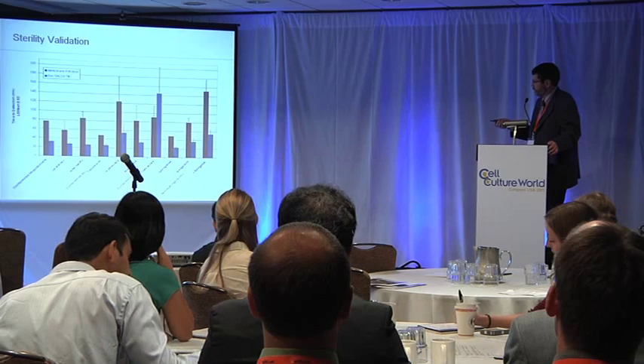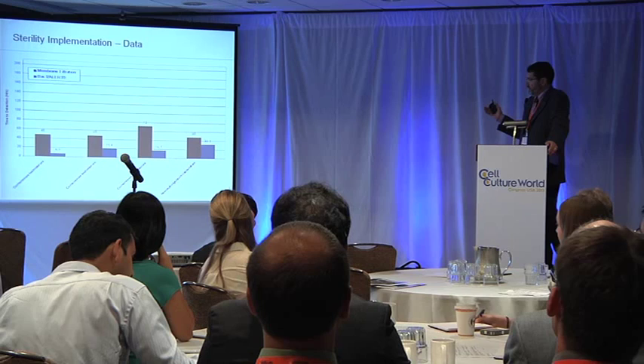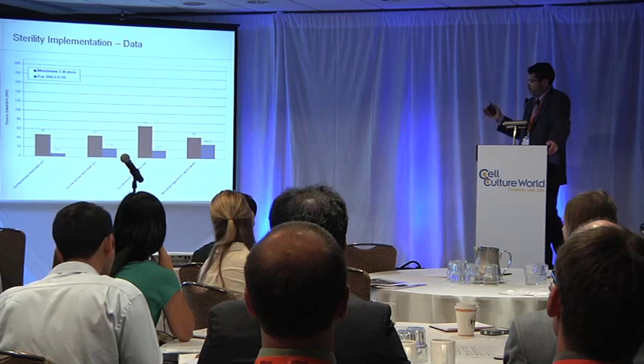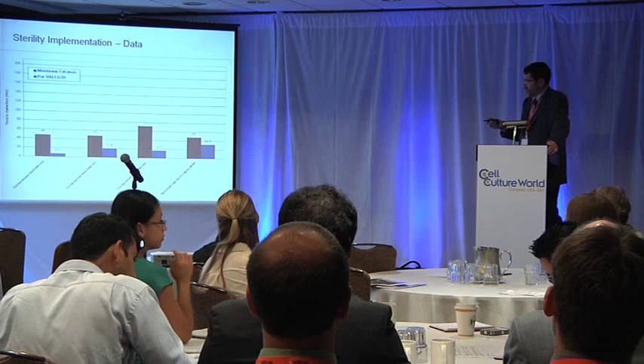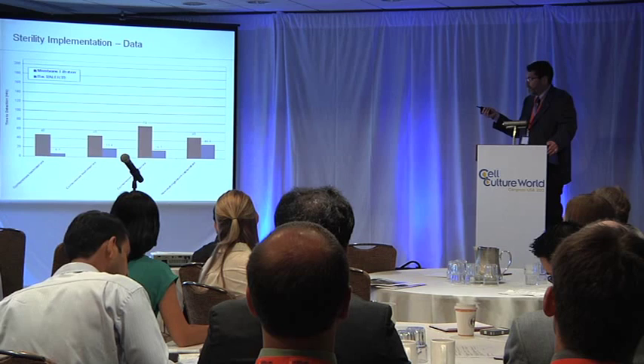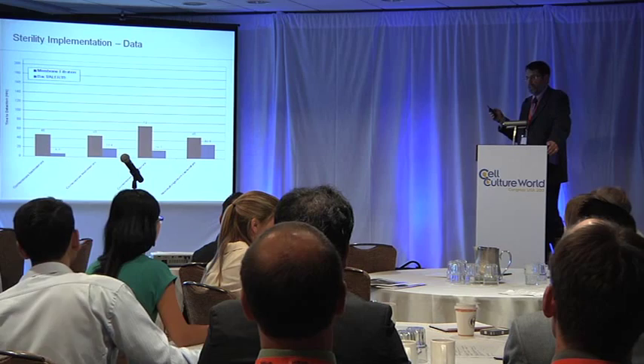For better or for worse, we also had the opportunity with some true contamination data to do some head-to-head comparisons of the BacT/ALERT to the membrane filtration test. We had committed that if we ever got a positive with the BacT/ALERT, we would also run it by the membrane filtration test to confirm the detection. And as you can see, in all four of these cases, the membrane filtration test took either 48 or 72 hours, and the BacT/ALERT was less than — well, 32 hours in one case, but in general, approximately a day.